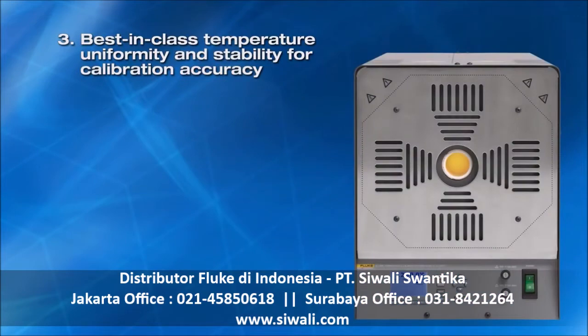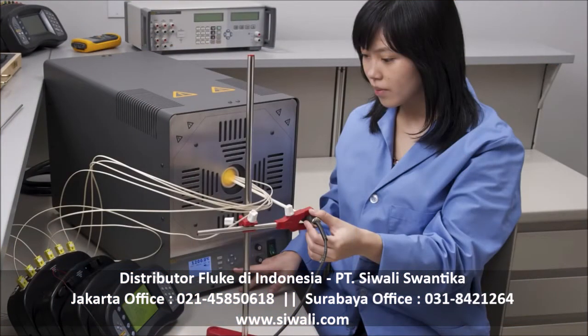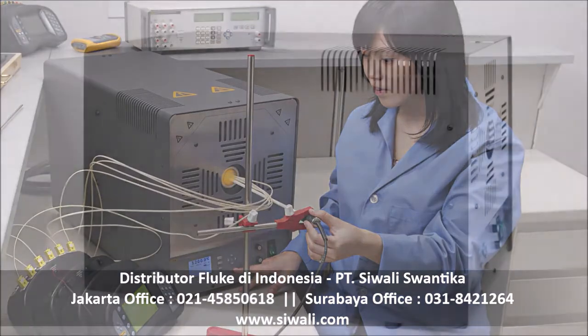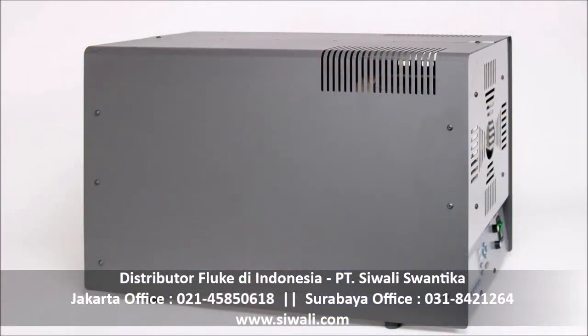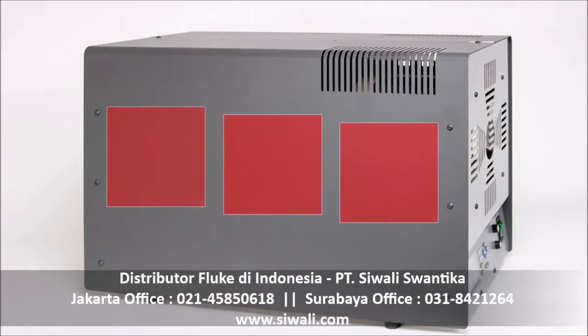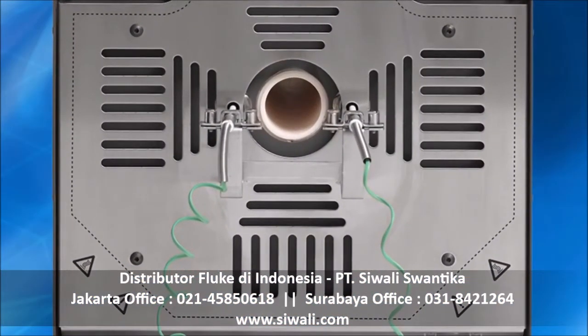Third, best-in-class uniformity and stability. Axial and radial uniformity, combined with a constant temperature stability over time, are key factors that contribute to accurate thermocouple calibrations. To minimize axial temperature gradients, the 9118A employs 3 independently controlled heater zones to compensate for temperature differentials between the central zone and the front and rear zones. Type S thermocouples, which are less susceptible to drift than other types, are used for zone control and cutout.